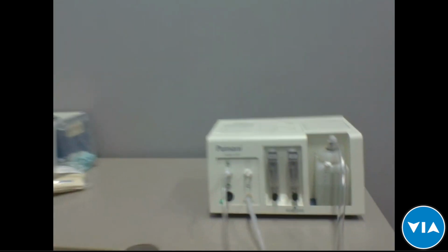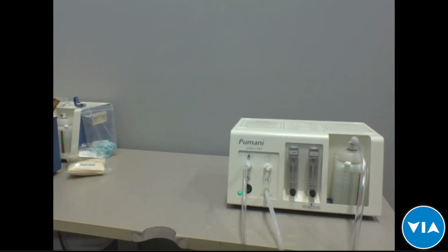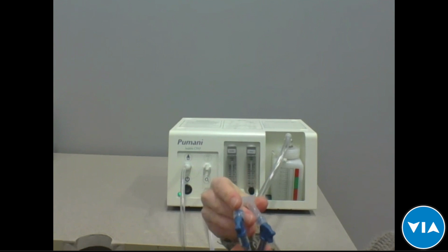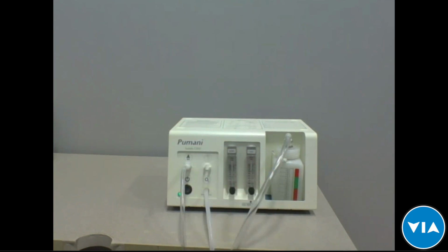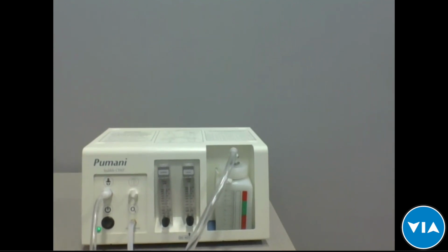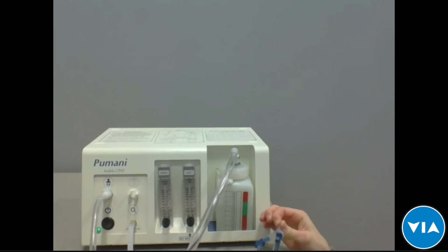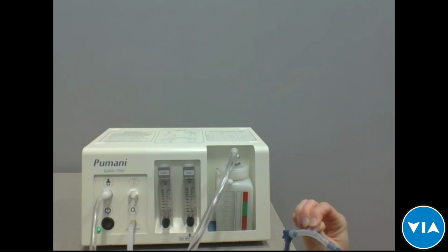So we have all that going, and then to make sure the whole circuit is working, the way we determine that is we need to check the bubbling function. To do that, you close the circuit, so you pinch the prongs as if they were in the baby's nose. And you'll see the bottle will start bubbling. Go closer. That means that there's CPAP being provided to the baby, because the entire circuit's closed, and that means that pressure, which is there to open the baby's lungs, plus the oxygen and air you put in, is actually getting to the baby. So that's the main functionality check. If that is bubbling, then everything in the system's working.